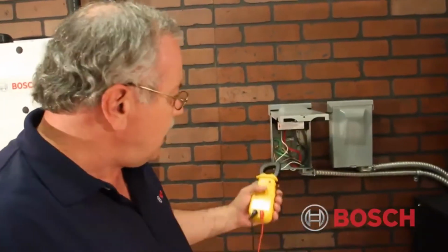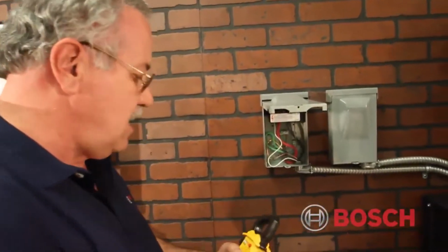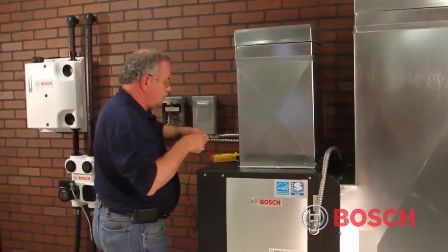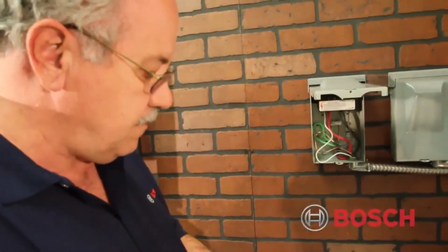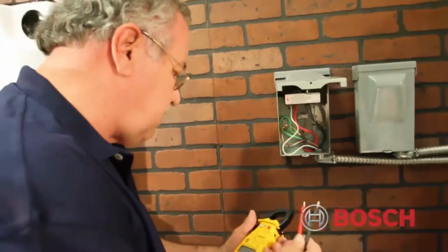Okay, while I have the heater energized and I'm taking the temperature difference between supply and return with the acceptable tools, I'll go to the disconnect for the heater, which I've removed the panel and opened the face. I'll take my voltmeter, set it to voltage. Any brand would work out there that's commercially available.